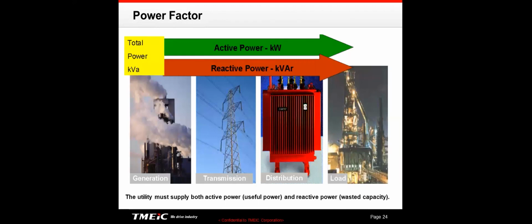In facilities, the utility has to supply the active power and the reactive power. That reactive power has to be generated in their generators, transmitted across their transmission lines, put through the transformers, put through the distribution system, and yet it doesn't actually generate real power. And so the higher the power factor, the lower that kVAR is going to be, and we'll be able to produce the same amount of load with a lower amount of current.